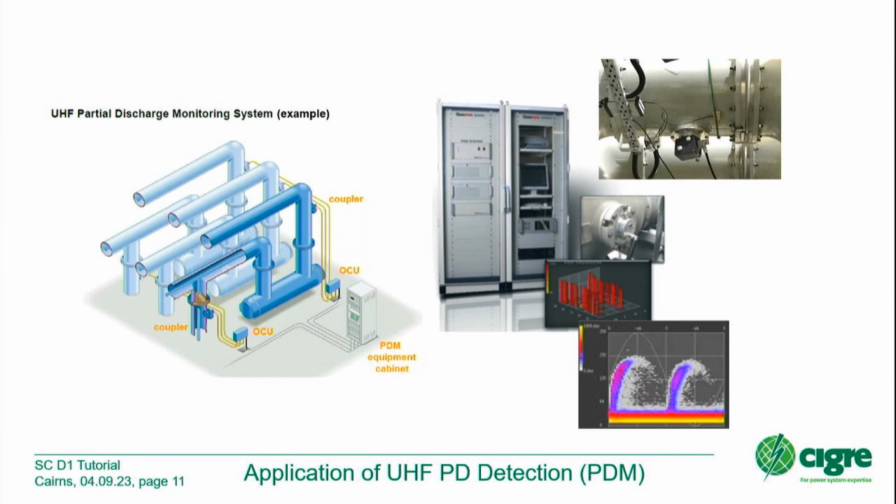So we are able to measure each partial discharge for, let's say, a time of 20 or 30 years, no problem about that. And let me say with that word, nowadays these systems are also really reliable. Yeah, in the beginning it was a little bit tricky. Electronics were not so good, software was not well. Anyhow, since roughly 20 years, these systems are on a very high level, which can support the utility when looking into the details of the GIS.